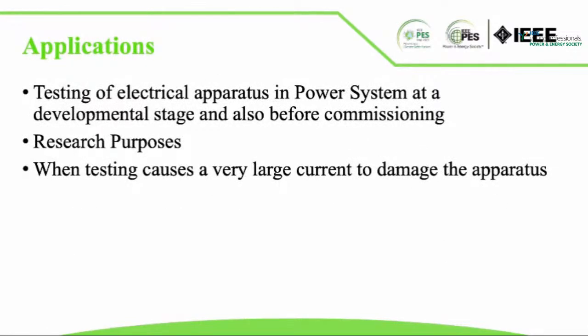Coming to the applications of high voltage testing, it is generally carried out on electrical apparatus at a developmental stage or also before commissioning. They are also carried out for research purposes, and the DC test is mainly carried out when an equipment can be subjected to very large current when tested with AC voltage, or which can cause a puncture to the system under testing conditions.